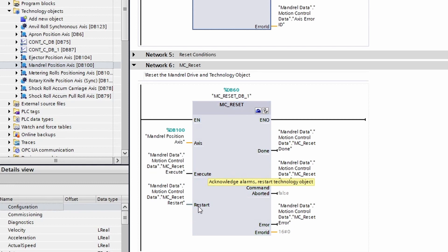If this execute is executed with restart being zero, it will do a fault reset on the drive and all the drive object associated parameters. That means if there's a fault on your drive, you can execute an MC_Reset and the technology object will reset that fault.